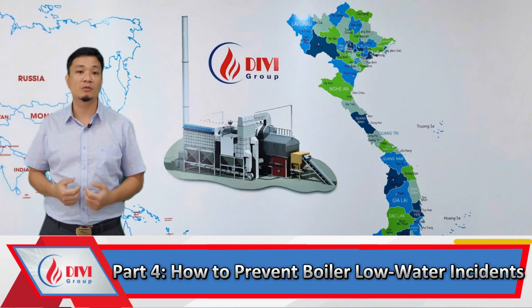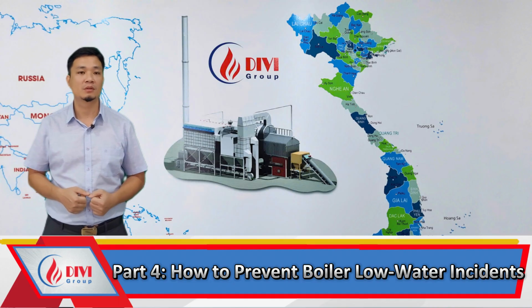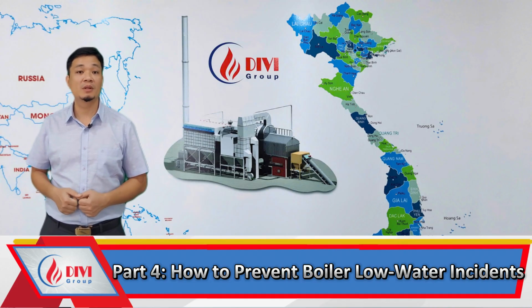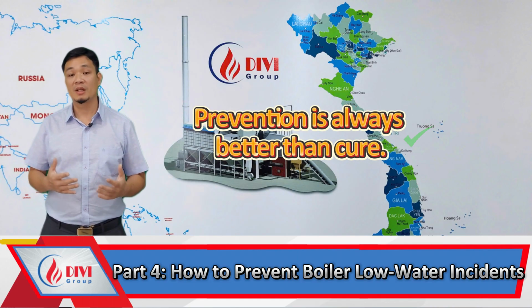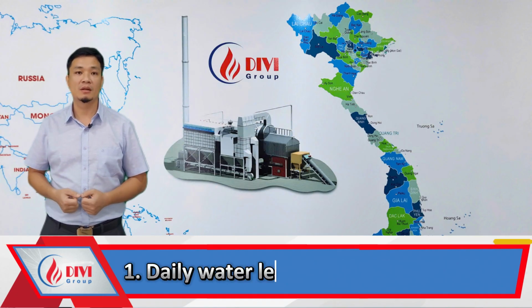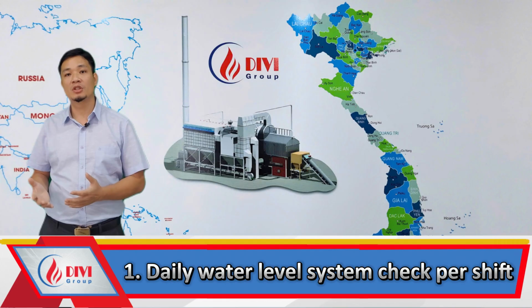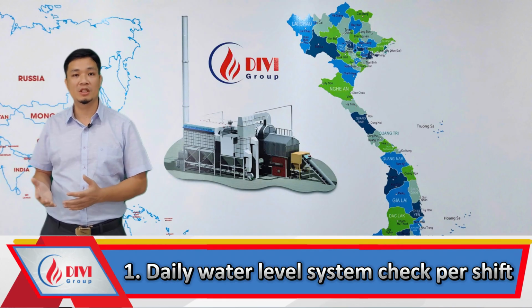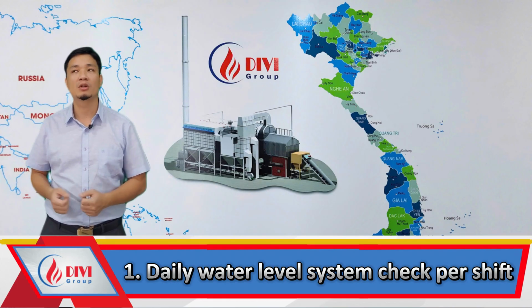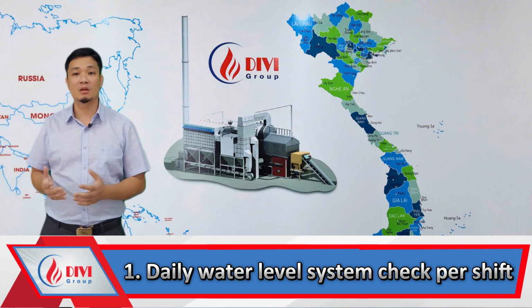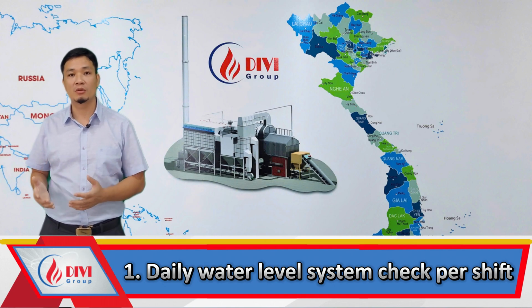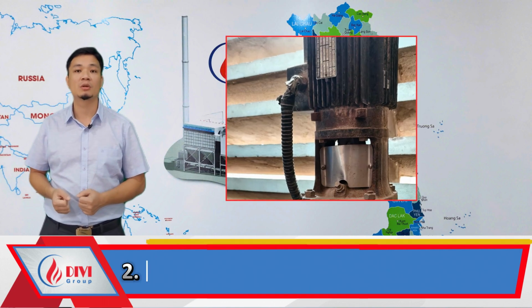Part 4. How to prevent boiler dryout incidents. Don't wait for an emergency to happen. Prevention is always better than cure. Focus on these 4 essential practices. Daily water level system check per shift. Inspect the water level sight glass, sensor calibration, and alarm functions. Refer to our previous DIVI video for a detailed guide on this procedure.